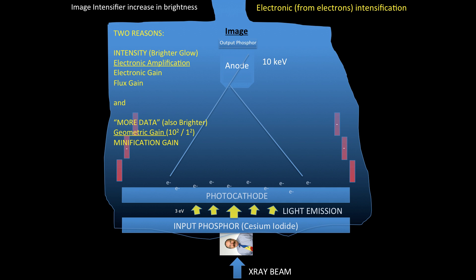So both geometric gain and minification gain are the same. They're just different names for the same process. I just gave you here a small example of the formula, so we have 10 squared, which represents my input phosphor, over 1 squared, which represents my output phosphor, and that gives you the measure or the calculation for the geometric gain that you generate as part of this process.